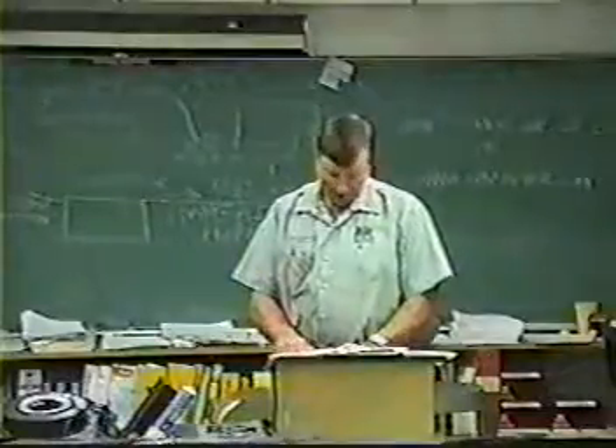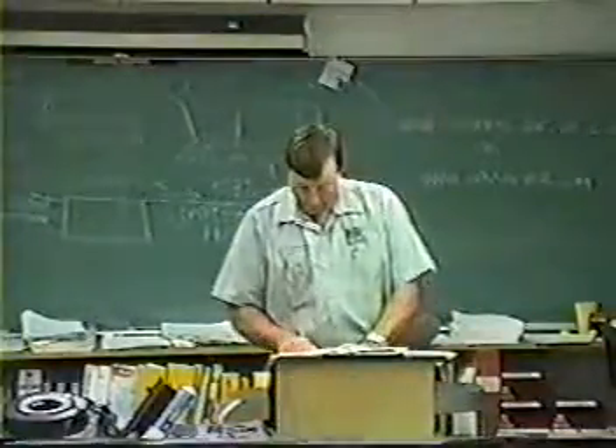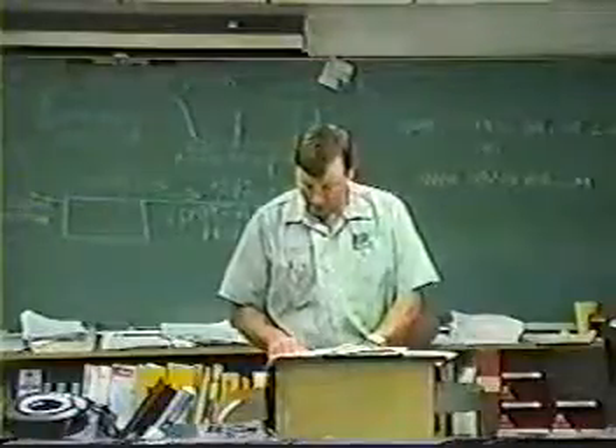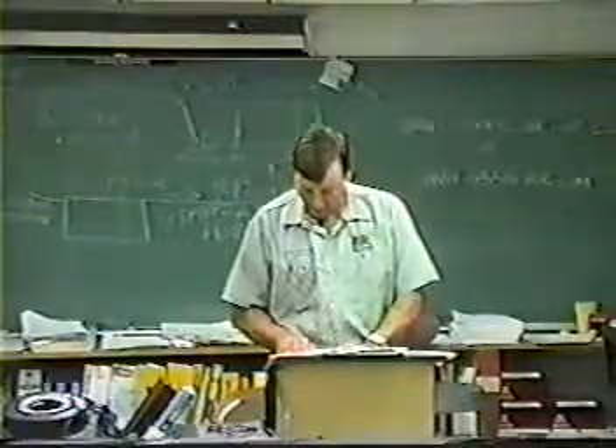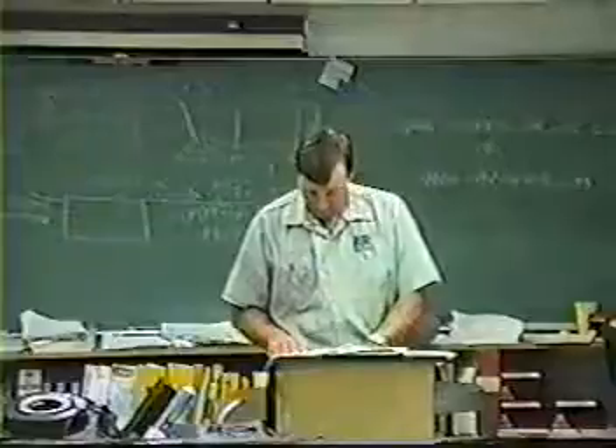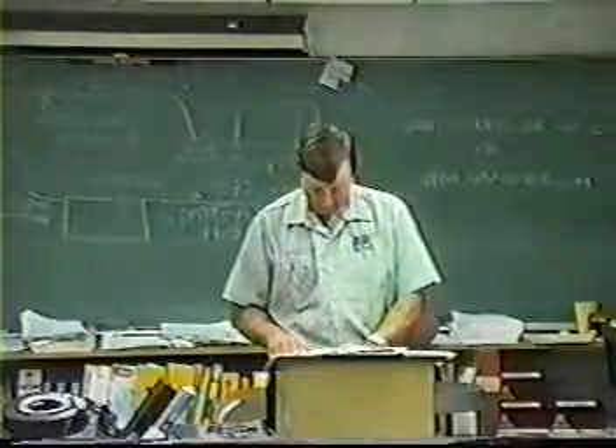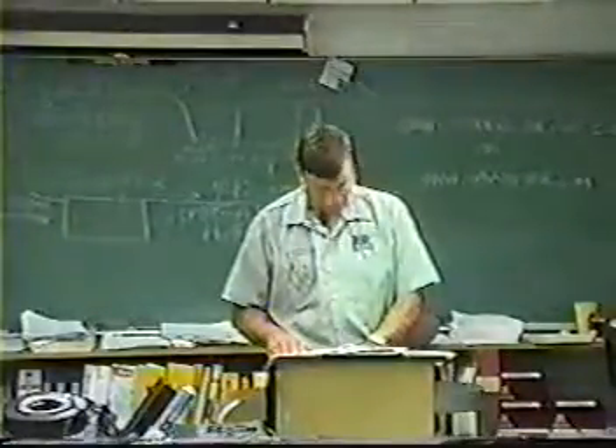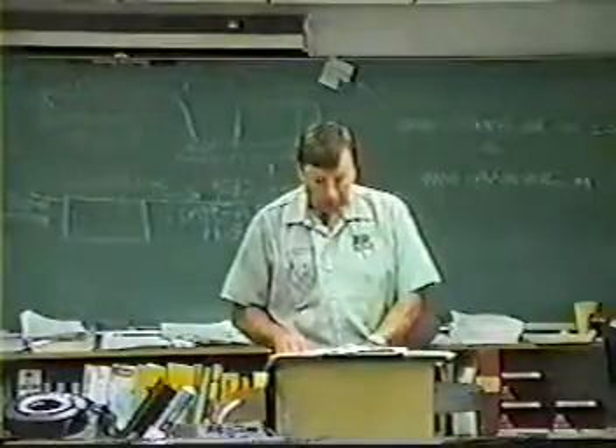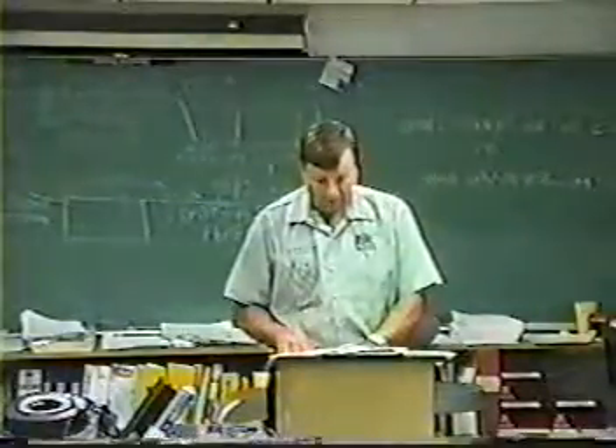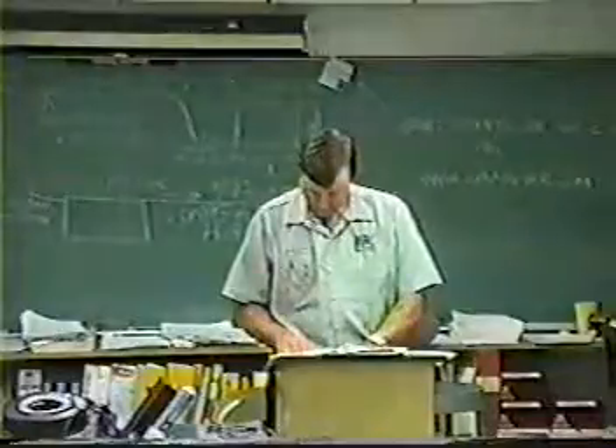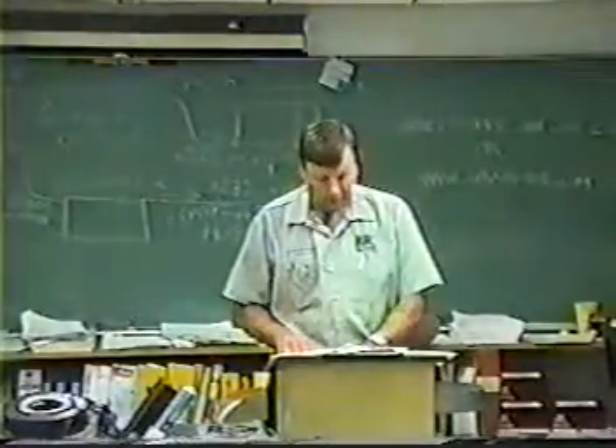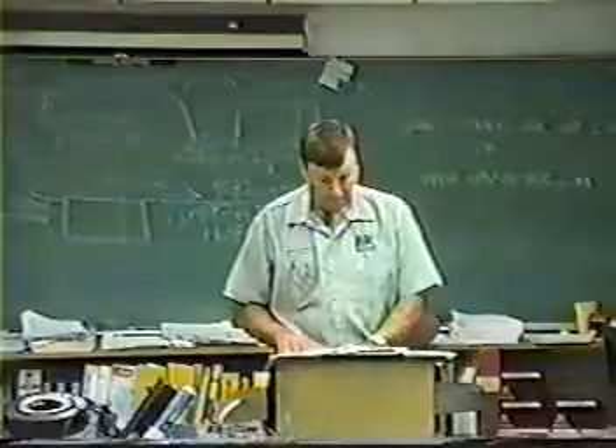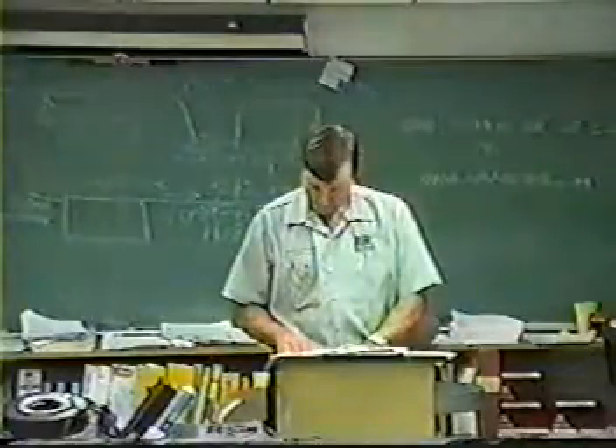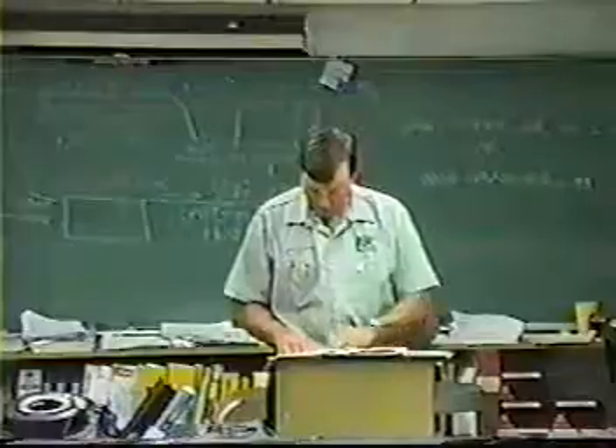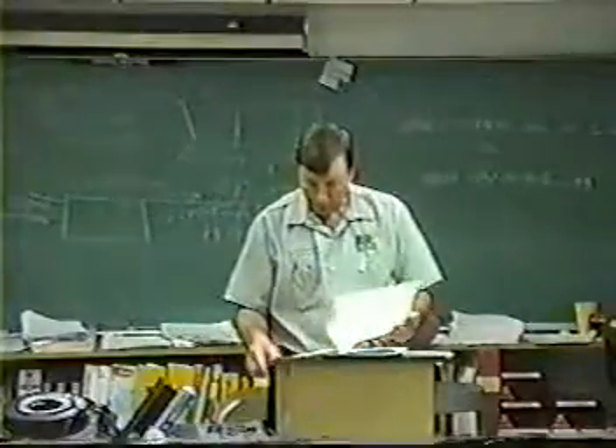The required level of evacuation for recovery equipment manufactured after November 15, 1993 on a system containing less than 200 pounds of refrigerant of R12 is what? See? 10. The key word here is after. It's less than 200 pounds. Okay. Any questions about that one now? Moving on, 59.